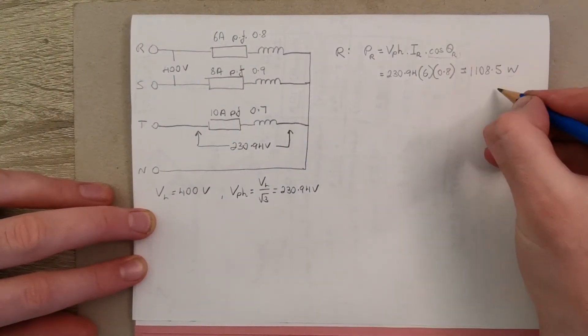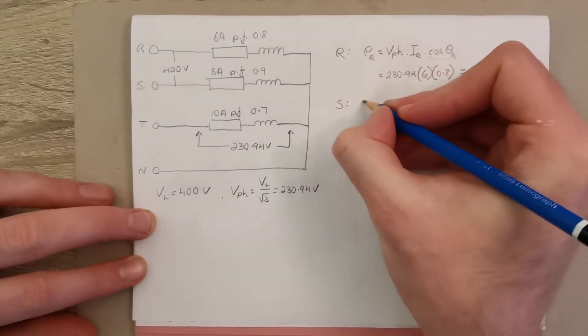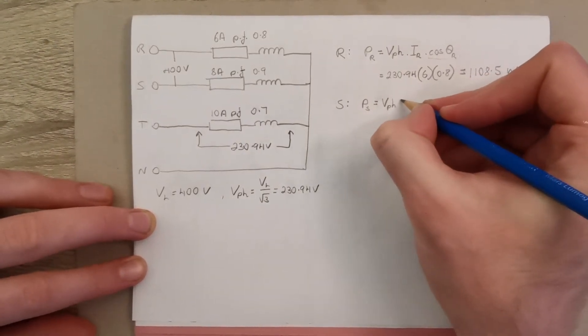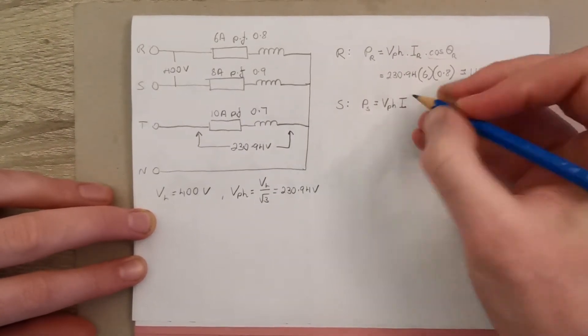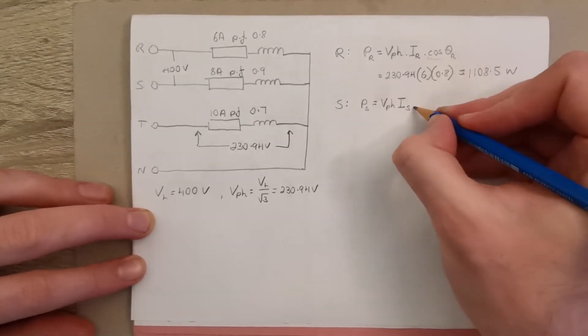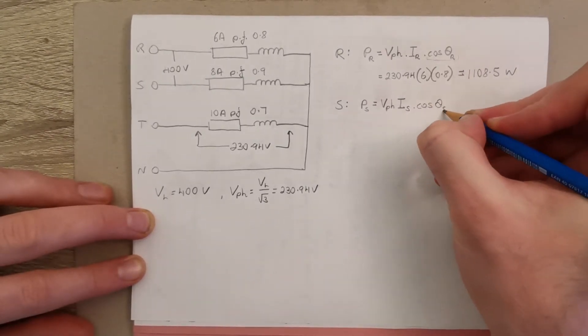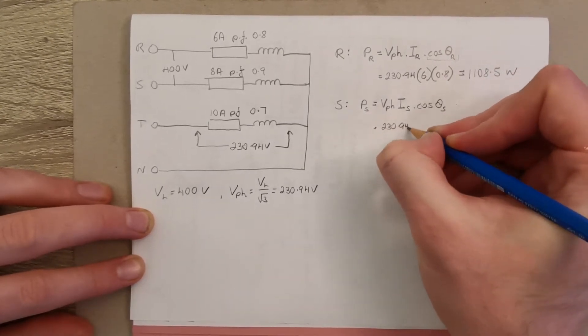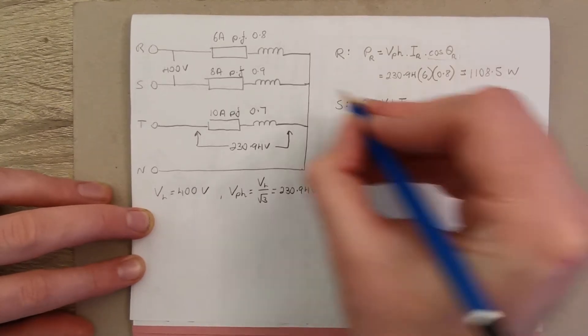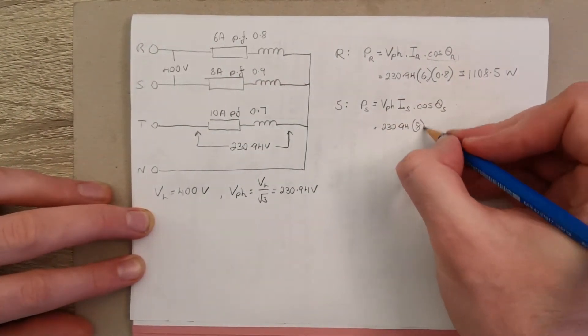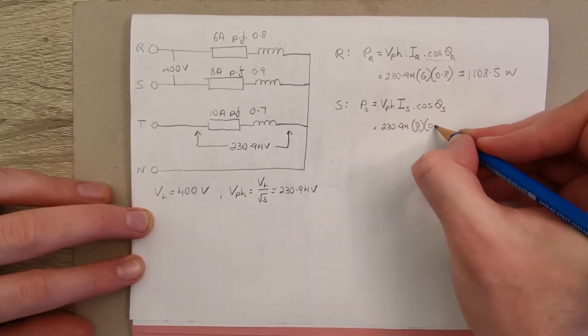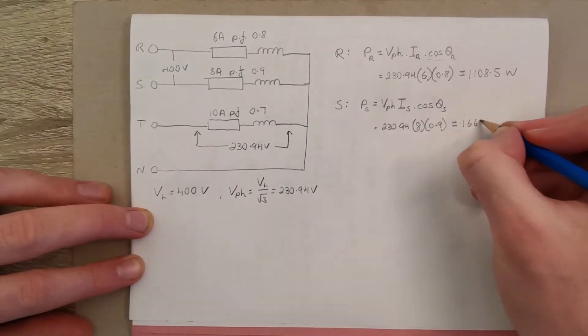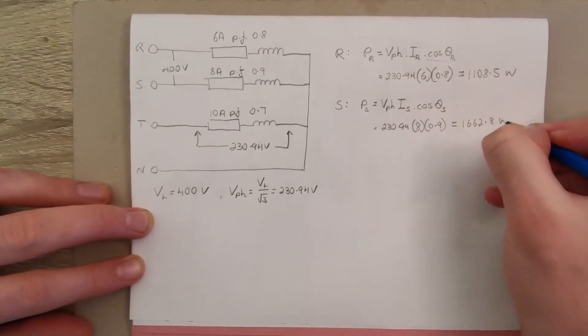Now we just repeat that process for each individual phase. Power in our S phase will be again the phase voltage times the phase or line current, they're the same here because it's star connected, times the power factor. So 230.94, line current here is 8 amps, power factor is 0.9, that works out at 1,662.8 watts.